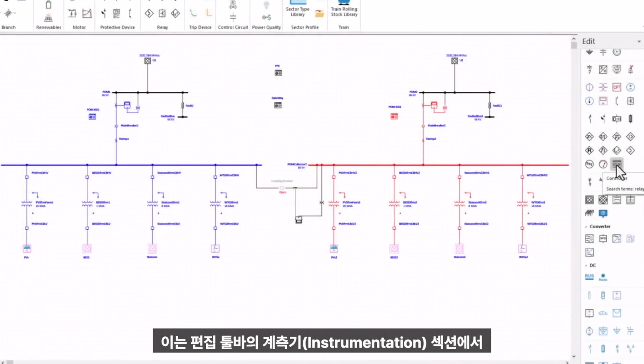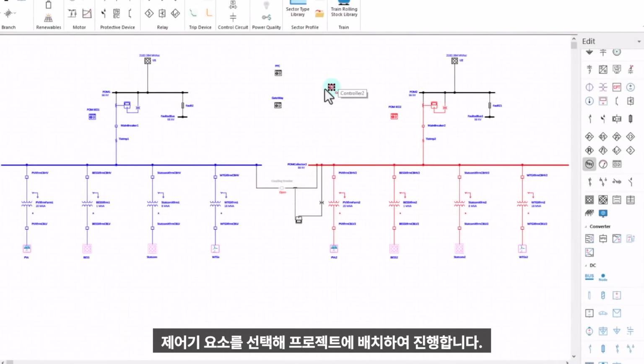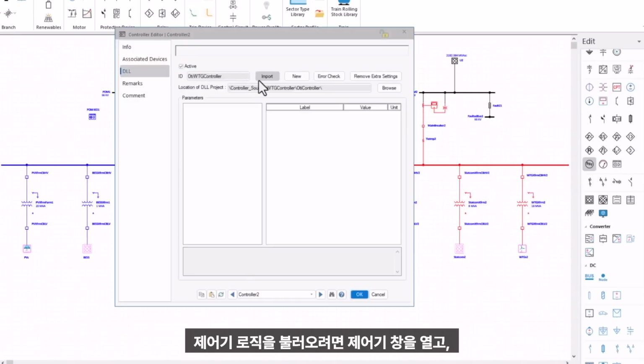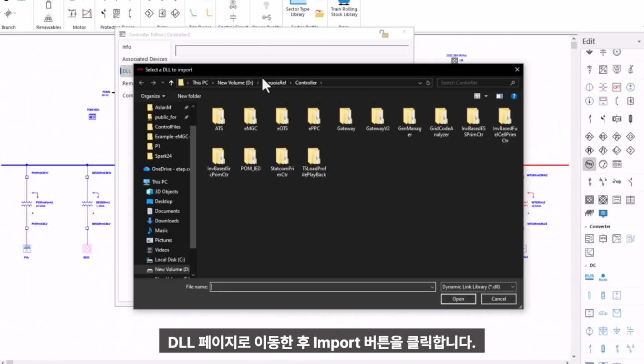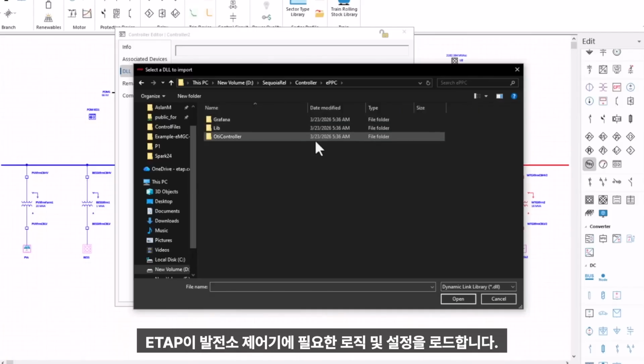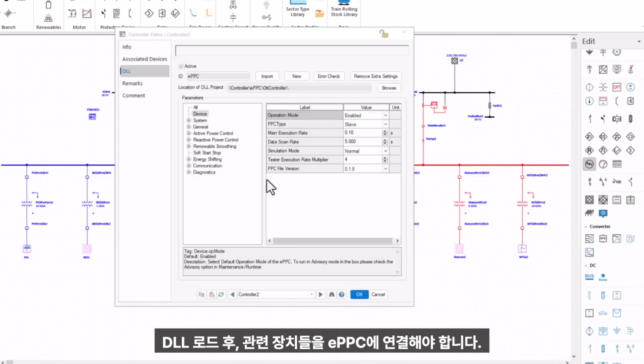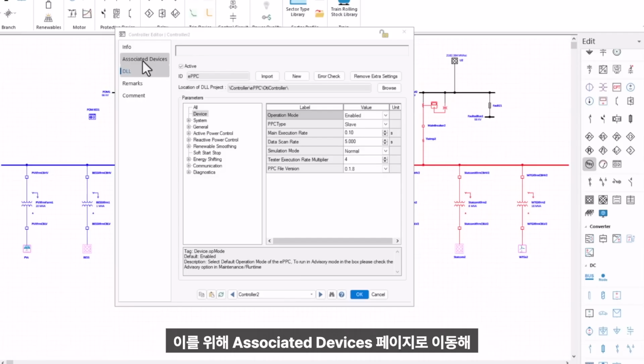This is done by selecting the controller element from the instrumentation section in the edit toolbar and placing it in the project. To load the controller logic, we open the controller, navigate to the DLL page, and click on the import button. This opens the ETAP folder where the controller logic is stored. From there, we select the ePPC OTI controller DLL, and ETAP loads the logic and the settings required for the power plant controller.